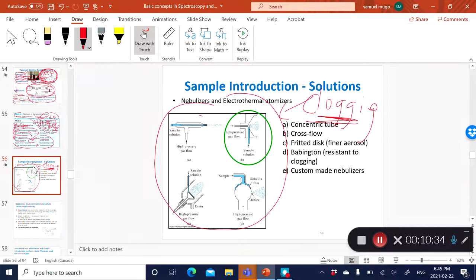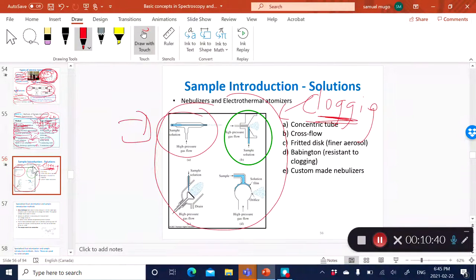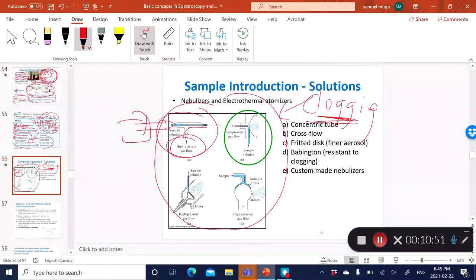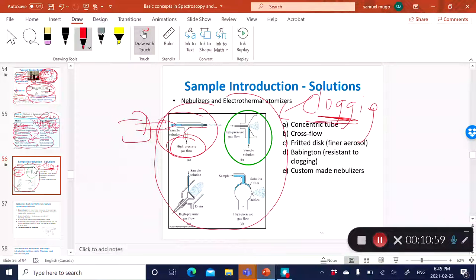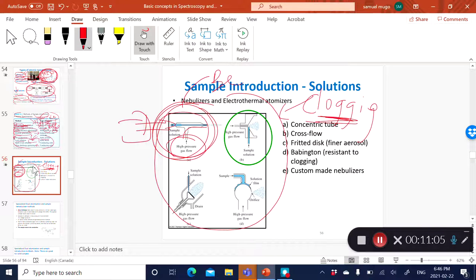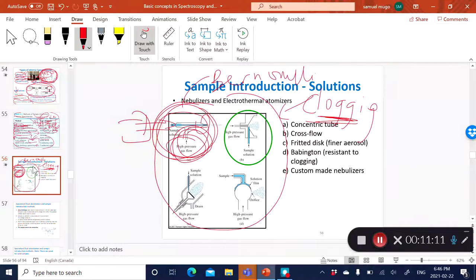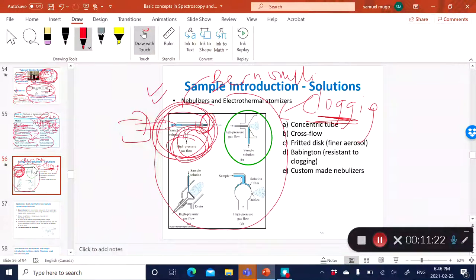One type of pneumatic nebulizer is the high-pressure gas flow, where a pump pushes the solution through a tube and gas moves around that tube, creating nebulization—a spray of that solution into a mist. This is what you refer to as the Bernoulli effect, where a high-pressure gas revolves around a concentric tube, creating suction. In this case, you don't really need a pump.